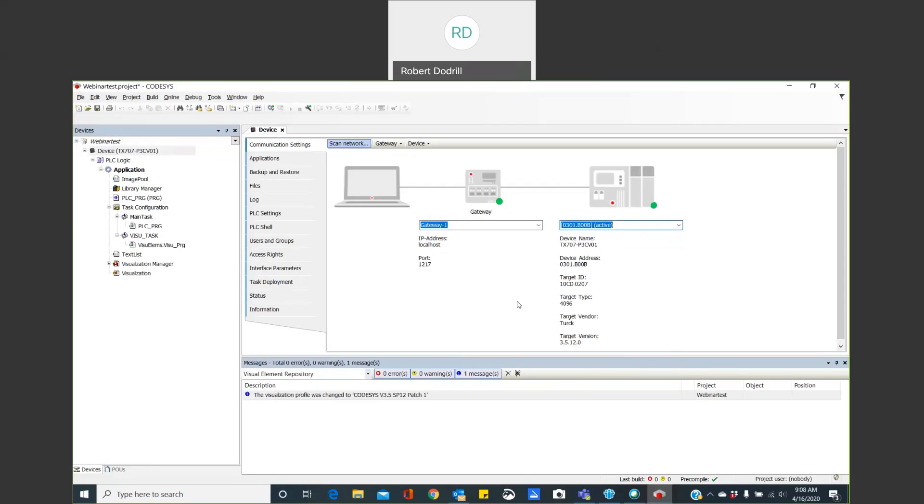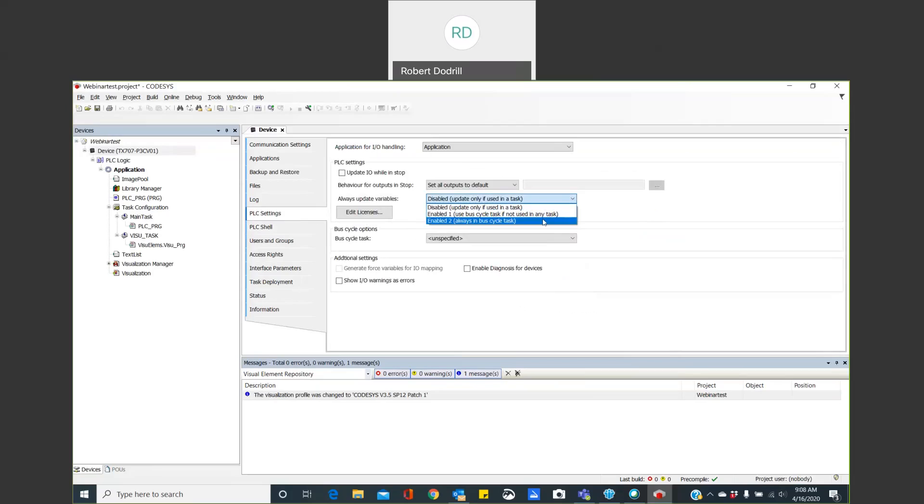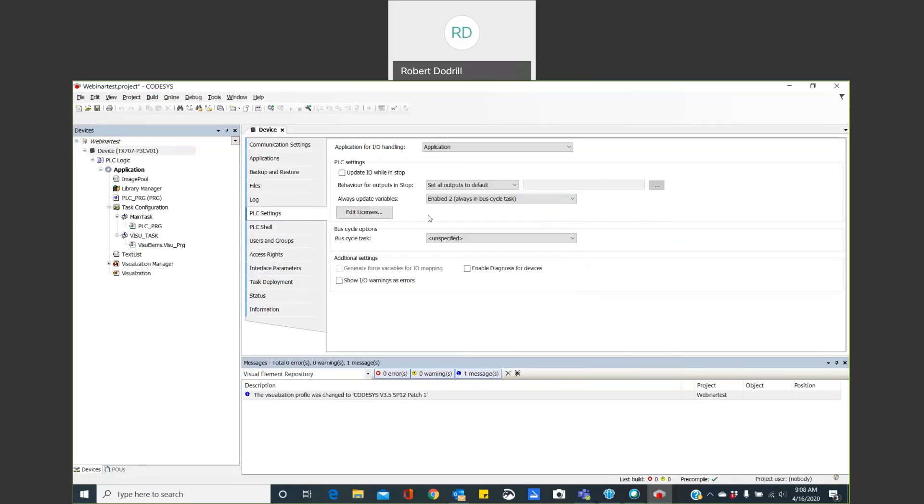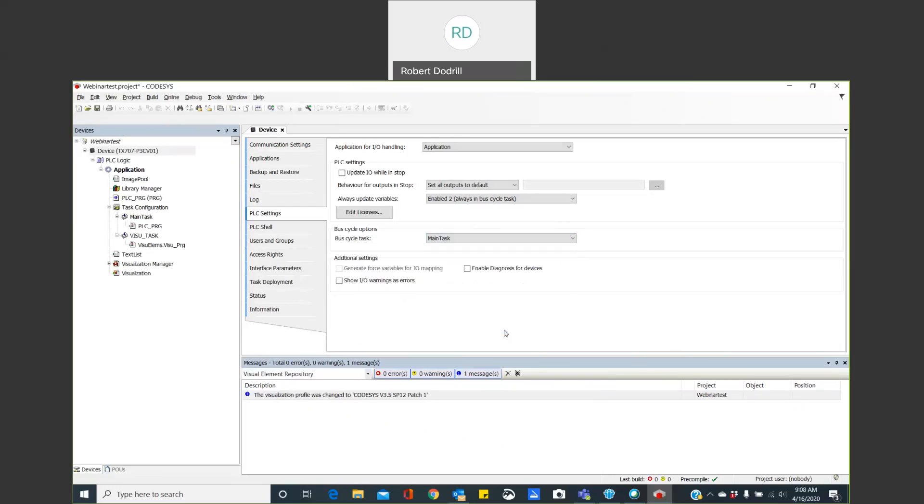Now, to start my new projects, one of the first things I want to do is go to my PLC settings. And right here where it says always update variables, if you'll set that to enable, then now all of my IO, once I start setting this up, it will follow my bus cycle task. And now I need to tell it what bus cycle task. So I want it to follow my main task. So my main task is everything's going to run right under this tab or under the main task tab. So now I've set up my communication channel, and I'm prepared to start adding things.